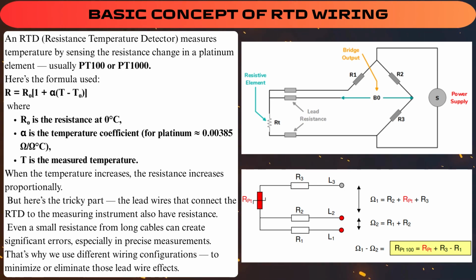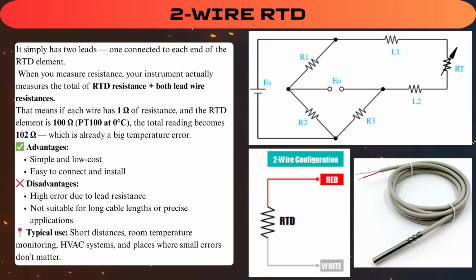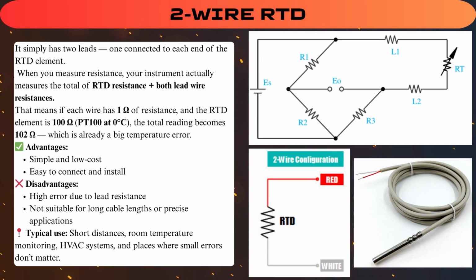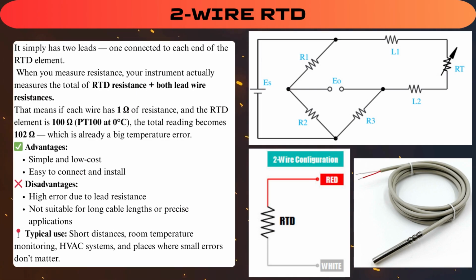But here's the tricky part: the lead wires that connect the RTD to the measuring instrument also have resistance. Even a small resistance from long cables can create significant errors, especially in precise measurements. That's why we use different wiring configurations to minimize or eliminate those lead wire effects. Let's start with the most basic, the 2-wire RTD.